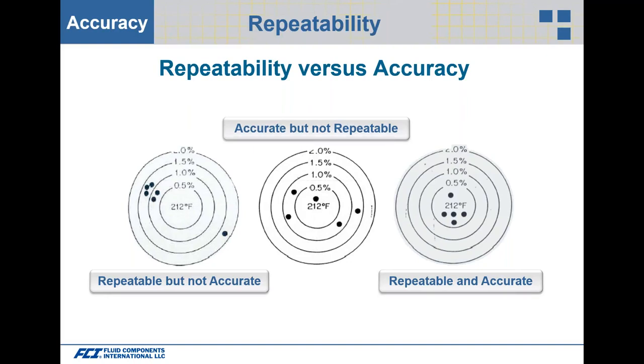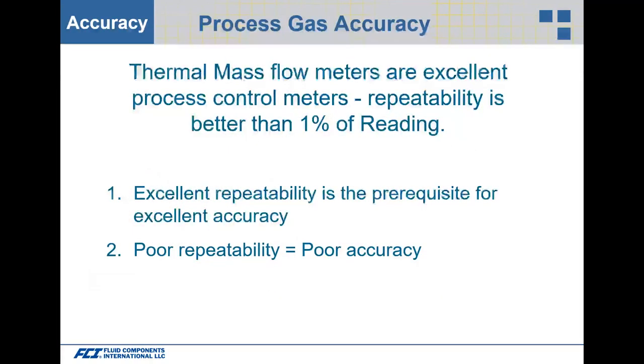Accurate but not repeatable shows a scattering around and in the bullseye. On the right-hand side we have repeatable and accurate. With thermal mass flow meters and air and gas, they're excellent process control meters — repeatability is better than one percent of reading, meaning those dots are all aligning repeatedly in the same area. Excellent repeatability is a prerequisite for excellent accuracy. Poor repeatability means poor accuracy.